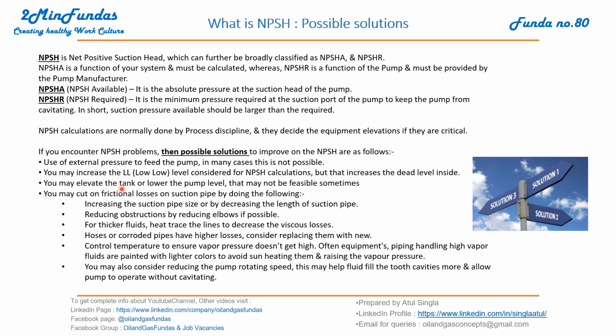The second one is you may increase the low level consideration for NPSH calculation, but that increases the dead level inside. This is a good solution, but it must be discussed with the vendor and process internally to finalize or implement this kind of solution. You may elevate the tank or lower the pump elevation. That may not be feasible sometimes.